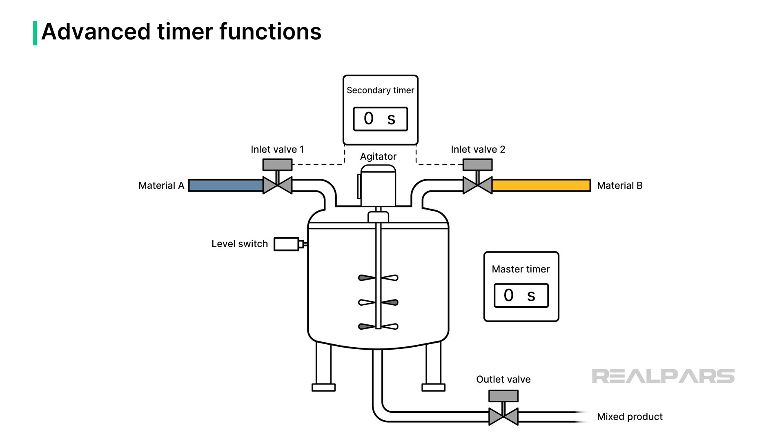Timers can be used for executing complex logic sequences. Timing functions can be cascaded to control the alternating addition of two feed streams into a mixing vessel, for a specific period of time. The master timer is set up for the overall addition time. A secondary timer controls the alternating opening and closing of the two ingredient valves.